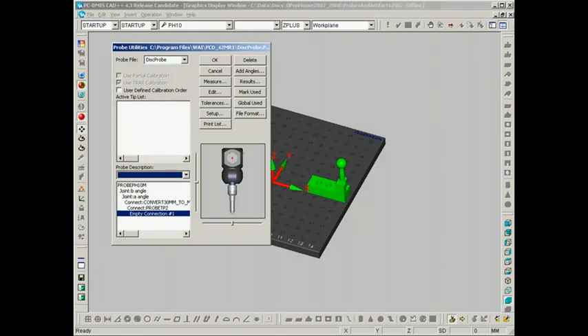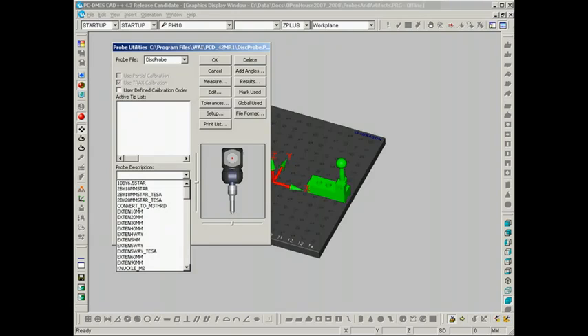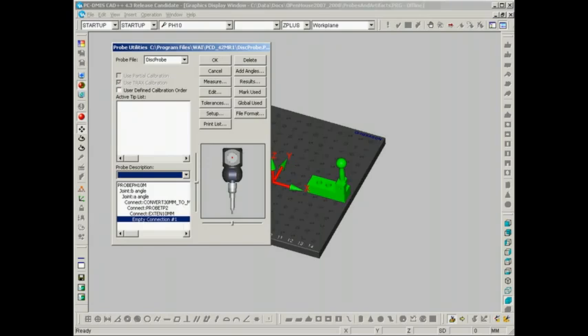So I've got my probe utilities window open, and I've got the beginnings of a probe buildup for this disc probe, all the way down to the TP2. What I want to do next is between my disc probe and the body of the TP2, I want to ensure that I have a small amount of extension. Usually 10 millimeters shall do it. So we'll select that 10 millimeter extension.